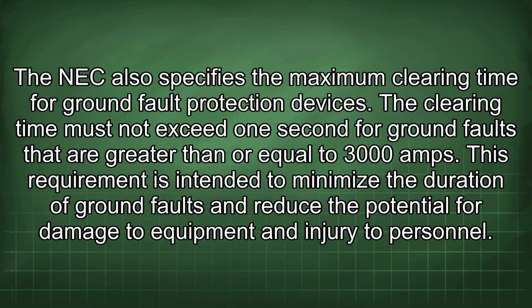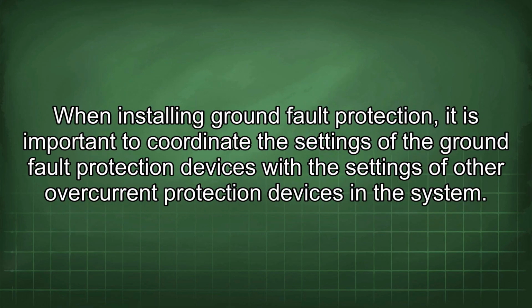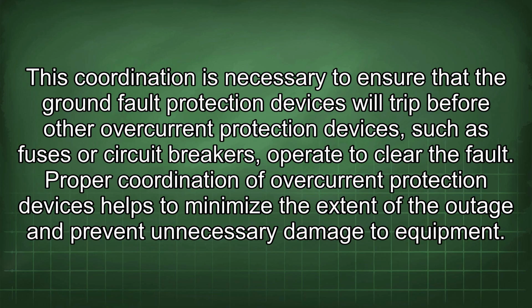This requirement is intended to minimize the duration of ground faults and reduce the potential for damage to equipment and injury to personnel. When installing ground fault protection, it is important to coordinate the settings of the ground fault protection devices with the settings of other overcurrent protection devices in the system. This coordination is necessary to ensure that the ground fault protection devices will trip before other overcurrent protection devices, such as fuses or circuit breakers, operate to clear the fault. Proper coordination of overcurrent protection devices helps to minimize the extent of the outage and prevent unnecessary damage to equipment.